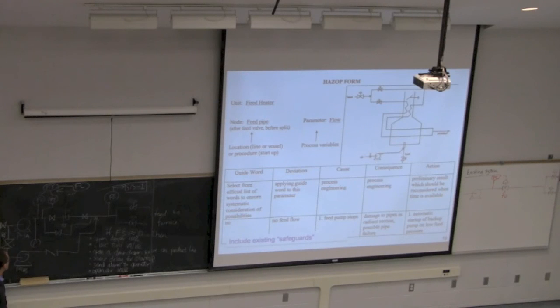Or the flow, either one would work, and then bring this down, and for that pump, have that hooked into the motor. So when this pressure reads low or zero, or this flow, you can use either P or F, so low pressure or low flow, then that motor kicks in. In that case, this becomes a PC or an FC. It's a controller of some sort, because it's taking action on that motor. It's going to start that motor when it reads low pressure. It's a very simple control.